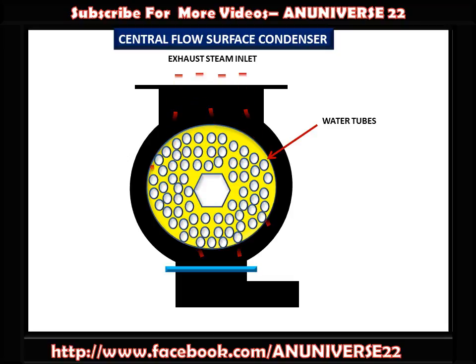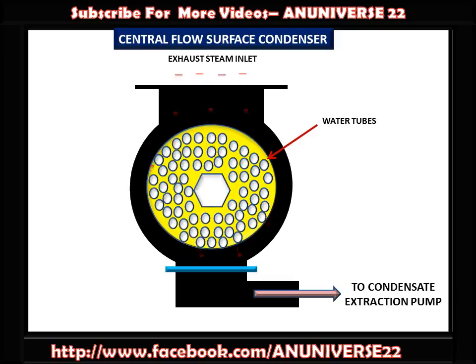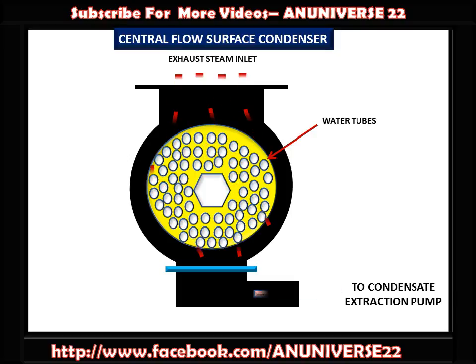The condensate is collected at the bottom and then pumped by the extraction pump, as shown in this video. The central flow surface condenser is an improvement over the downflow type, as steam is directly directed radially inward by a volute casing around the tube nest, giving access to the whole periphery of the tubes.